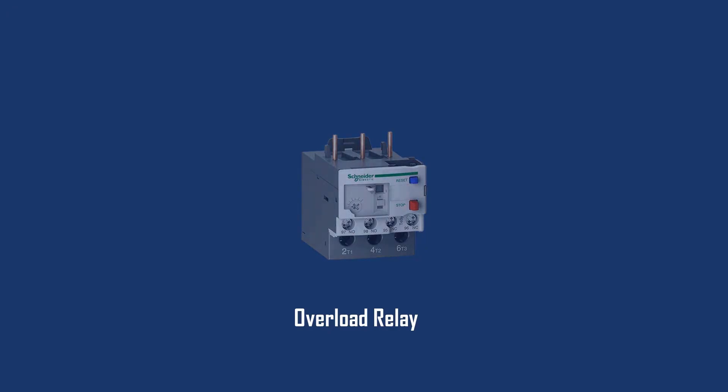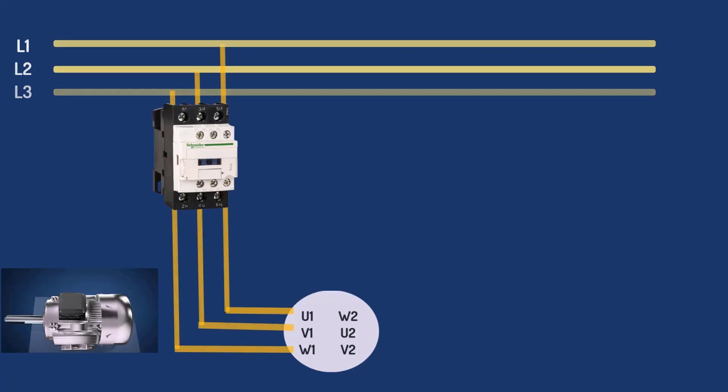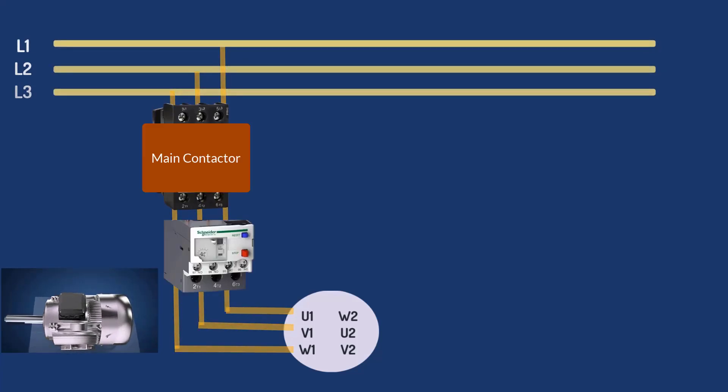Overload relay protects the motor, motor branch circuit, and motor branch circuit components from excessive heat resulting from overload conditions. They protect the motor by monitoring the current flowing in the circuit. If the current rises above a certain limit over a period of time, then the overload relay will trip. We will add an overload relay here into the circuit to provide better protection for the motor.